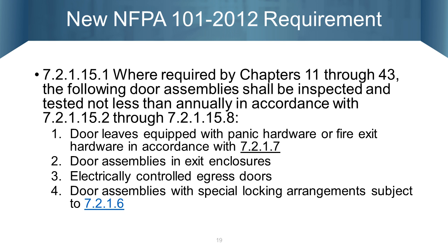I think we're going to find doors with holes in them, frames with holes in them, improper hardware attached, and we'll have lots of repairs and probably door replacements that will have to be made as we make this review. But after that, I think once that's done, I think then we'll be able to maintain them from there on out. The other thing is, we can't just have anyone do this inspection. It has to be someone that's been specifically trained. So if you're going to use your staff, make sure you send them to a seminar and you can document that so you can show that they've been trained to do these door inspections.